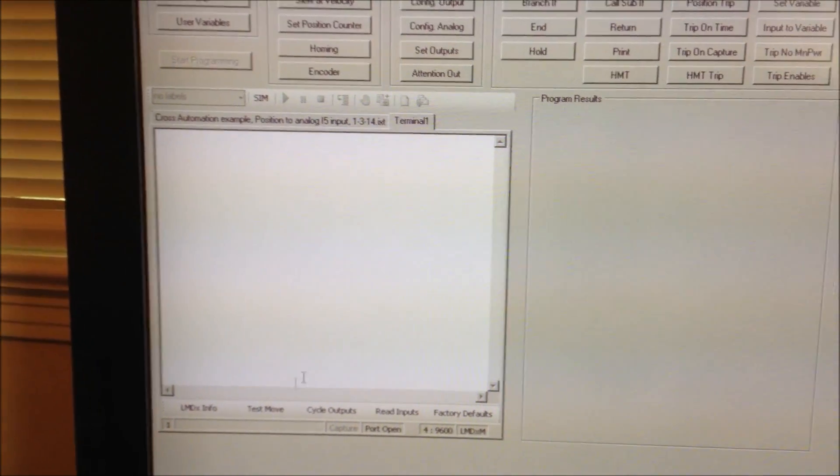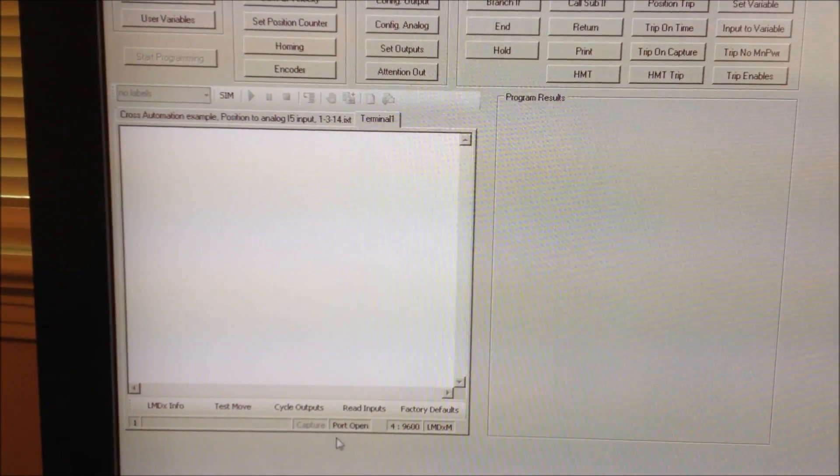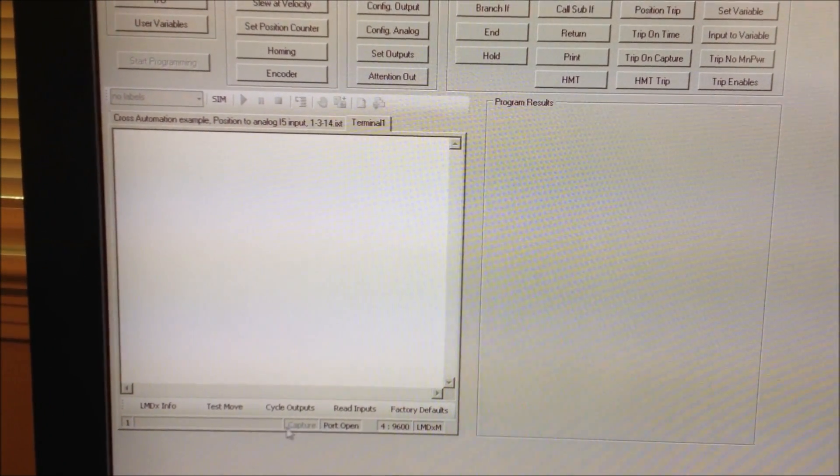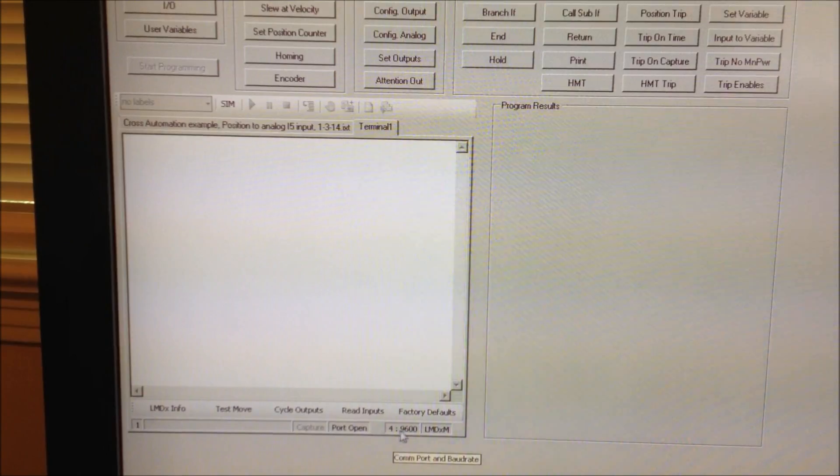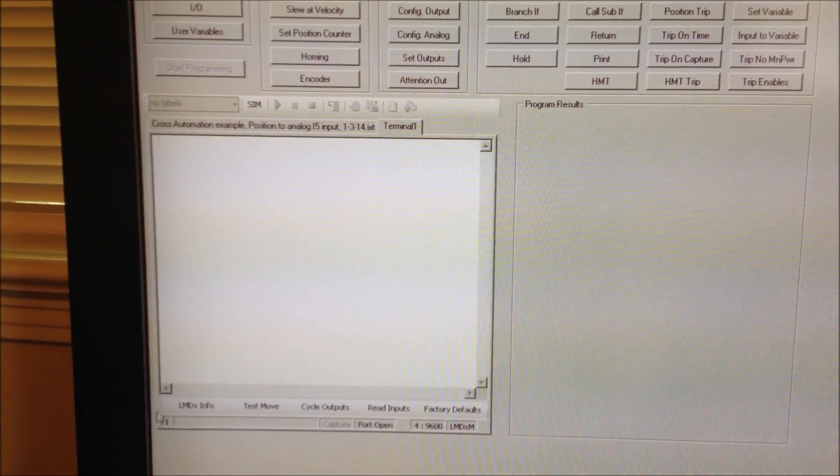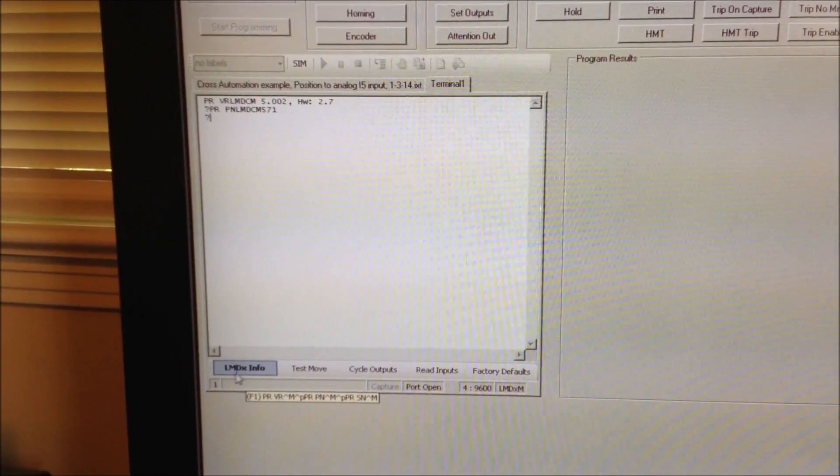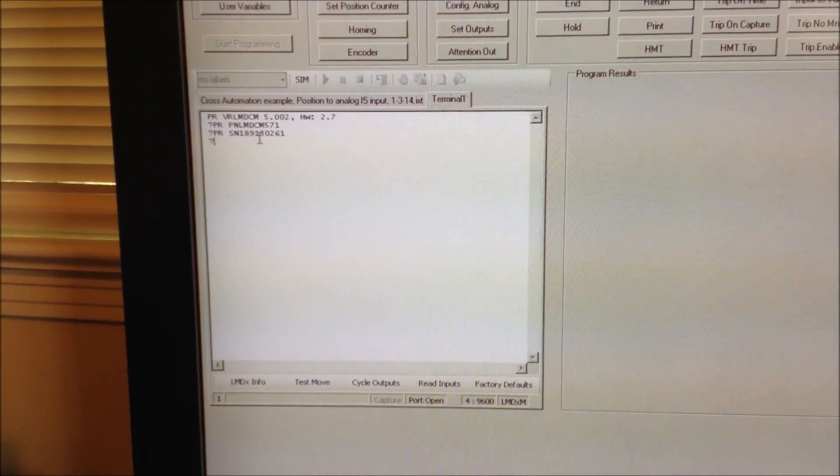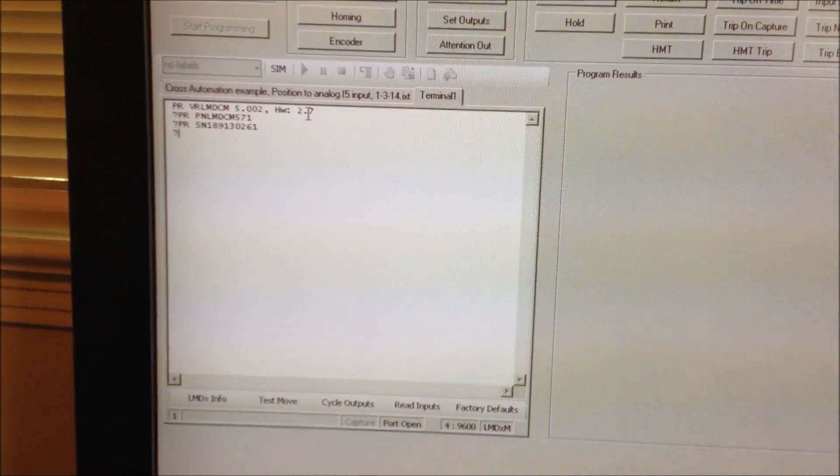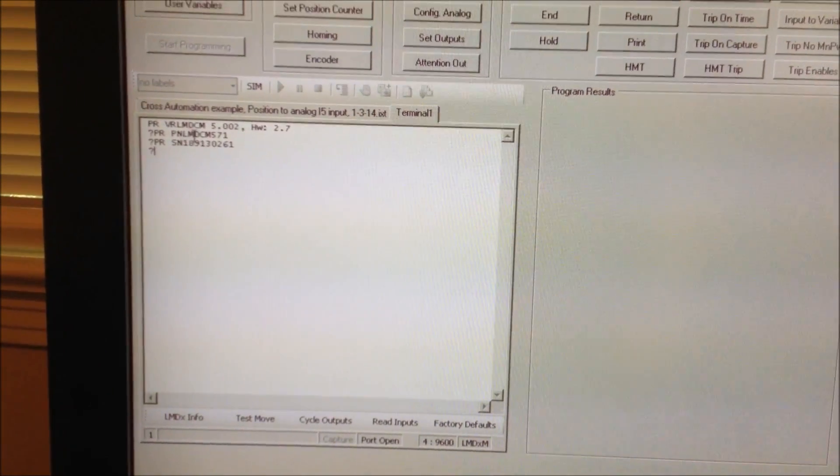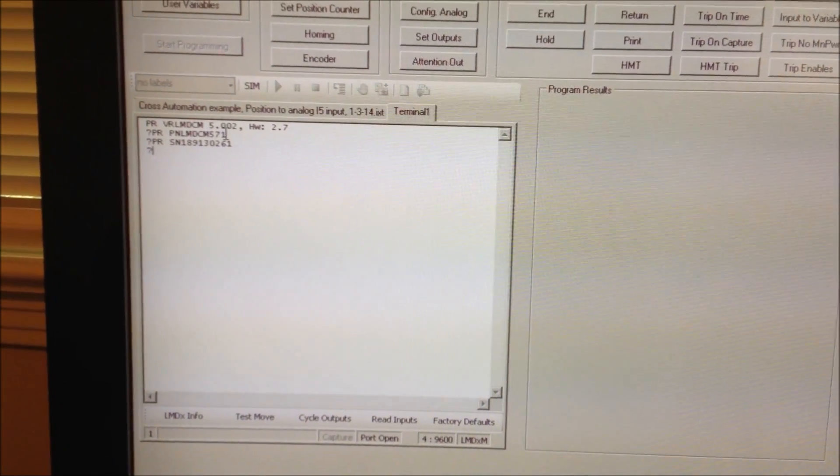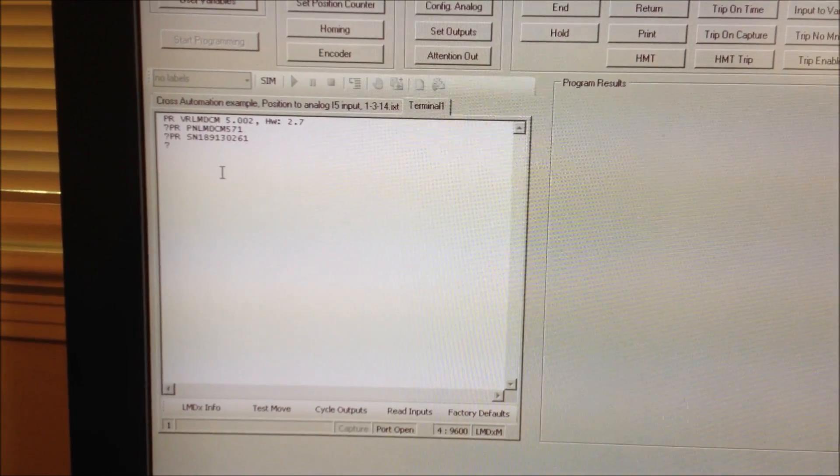Just to make sure it's communicating, I see the port is open. It's port 4, 9600 baud. I'm going to type this button here and it's going to come back and tell me here's my hardware. This is the unit model number and the serial number. So it is communicating.